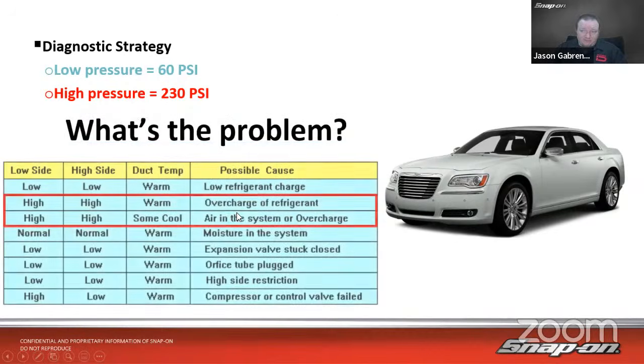So what's the problem? Let's look at a little diagnostic flow chart. If the low side is high and the high side is high, which is the case, it could be either of these two things. If both are high and the temp is warm, it's an overcharge. If both sides are high and there's some cool, it's not quite there, it's either air in the system or an overcharge. Either way, we're probably looking at an overcharge, or if anything, air in the system. We can see the other conditions too. If both are low and it's warm, an expansion valve stuck closed could be a problem, or orifice tube plugged, high side restriction, compressor, etc. In this case, it's high, and some cool is what we're looking at.